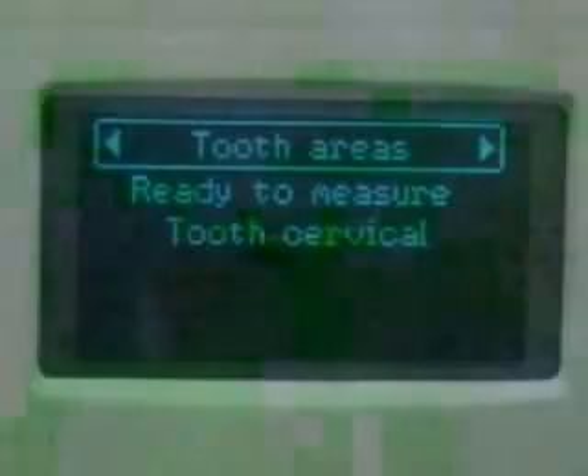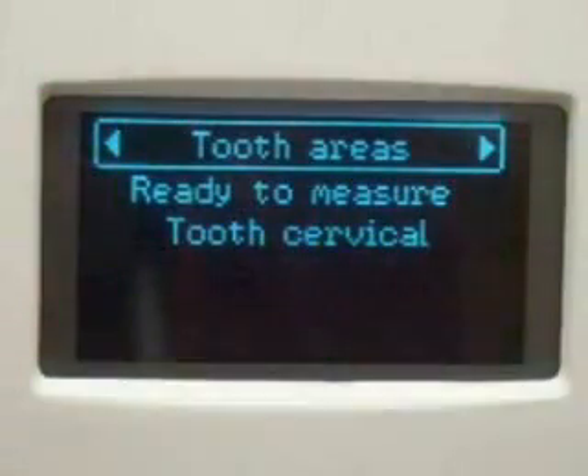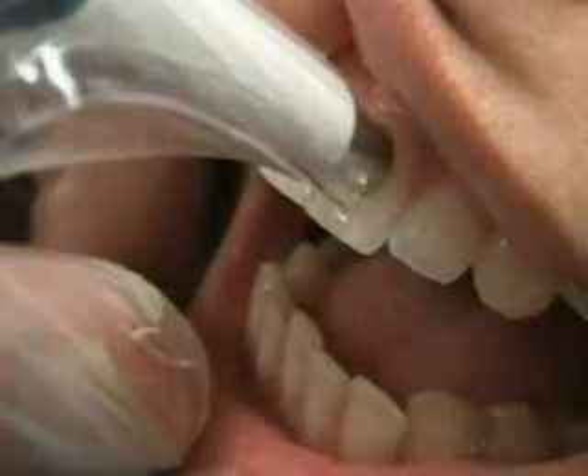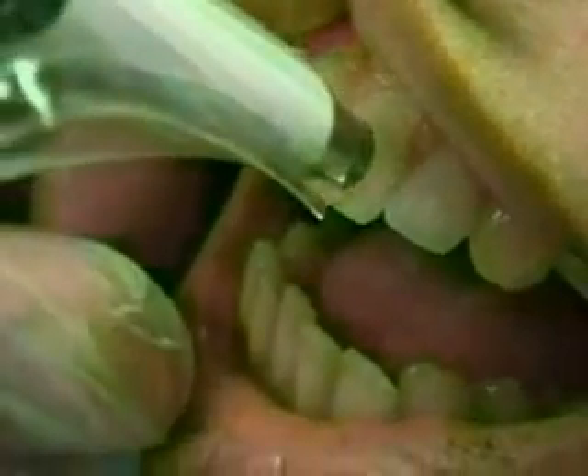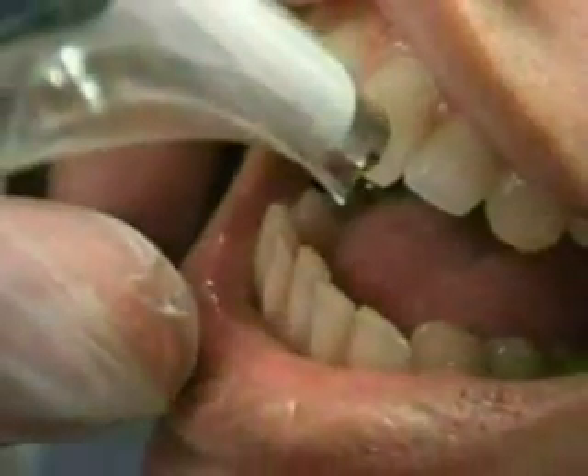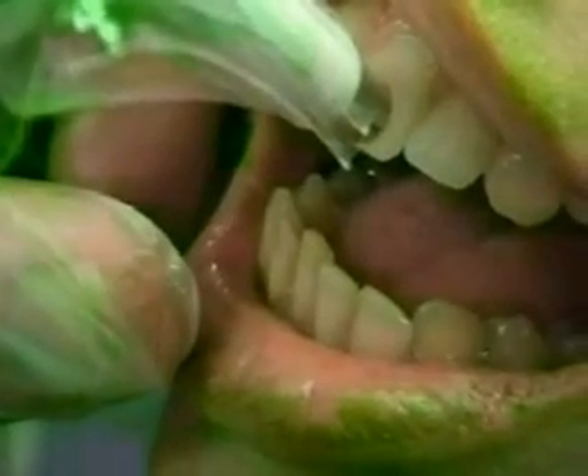The Easy Shade also has a setting to allow you to create a shade map by dividing the tooth into 3 separate tooth sections: cervical, middle and incisal areas. When measuring the cervical area of the tooth, make sure that the probe tip is in contact with the tooth at least 2 mm from the gingival tissue. When measuring the incisal edge of the tooth, make sure that the probe tip is at least 1 to 2 mm from the edge of that tooth.